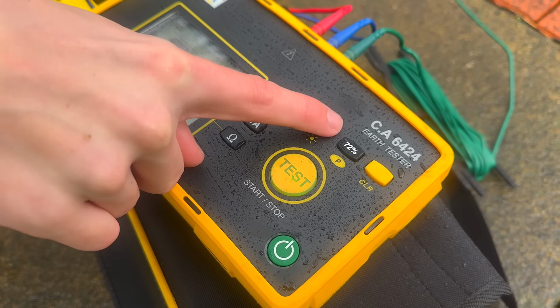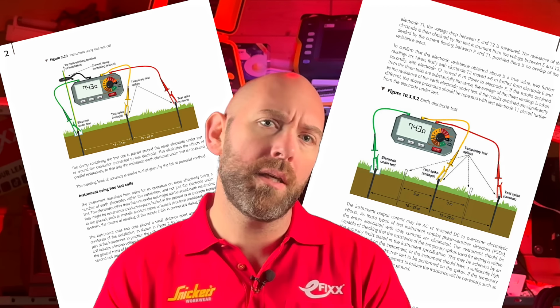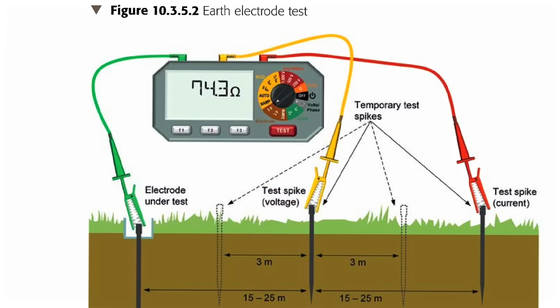But here's a question that baffled me. Why is it 62% for the potential probe? I always thought it was halfway. I mean, Guidance Note 3 and the on-site guide both say that you put the potential probe halfway between the current probe and the electrode under test.